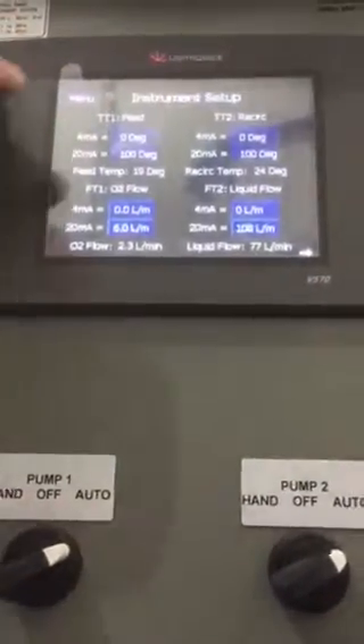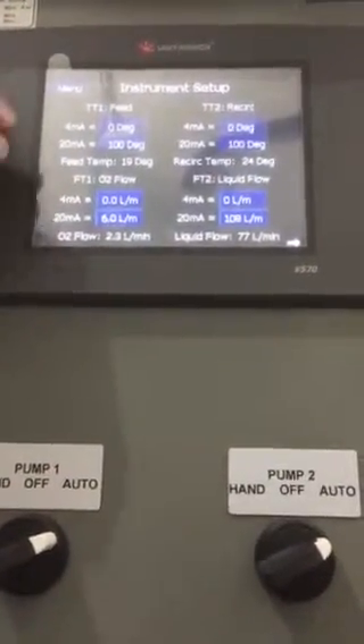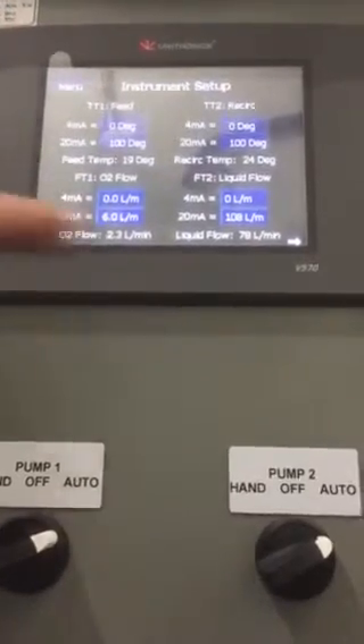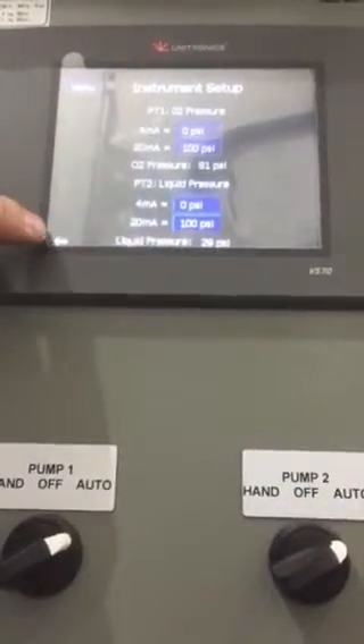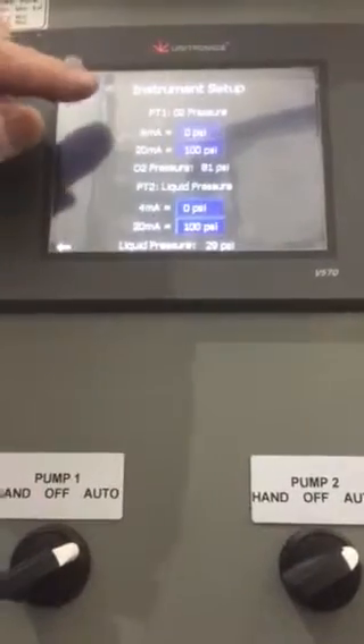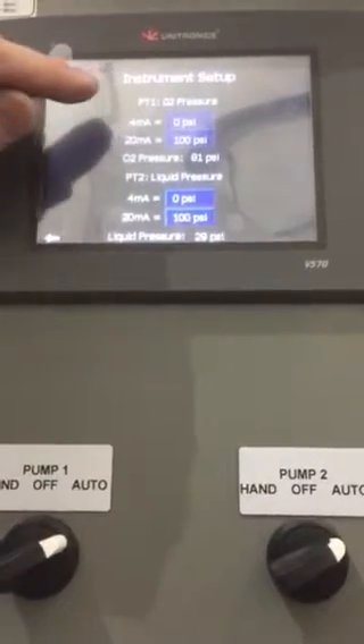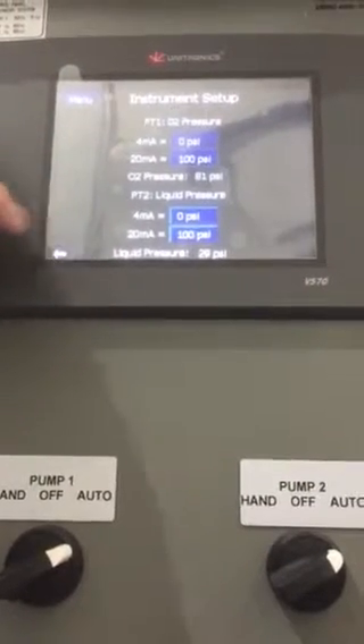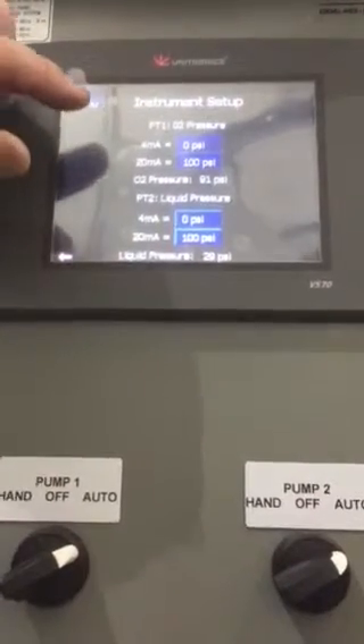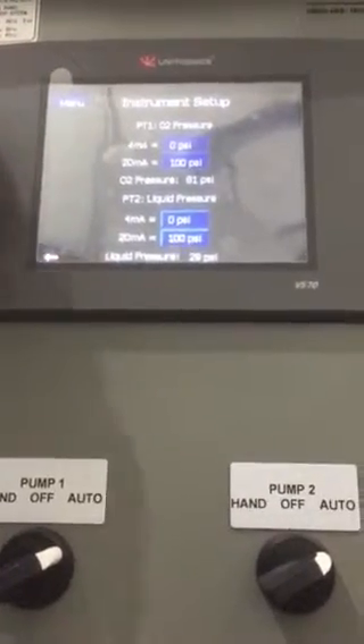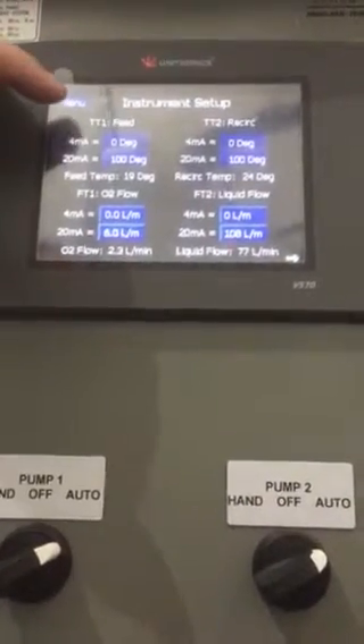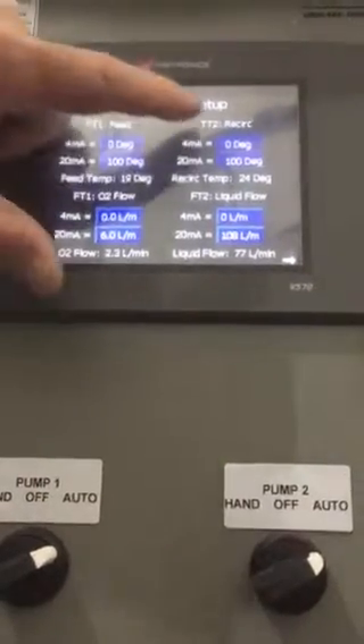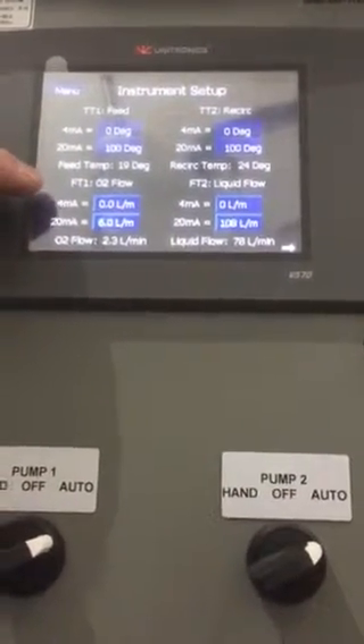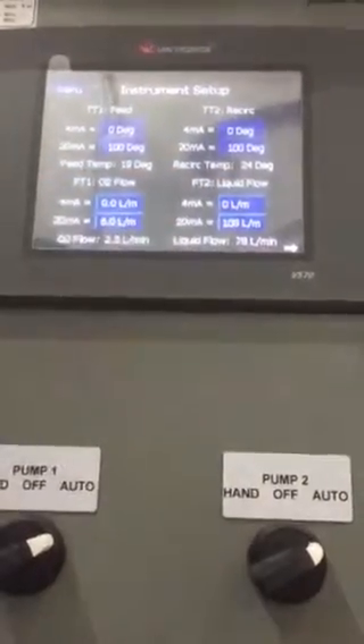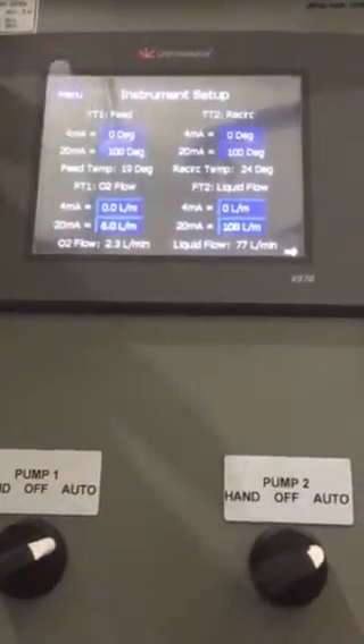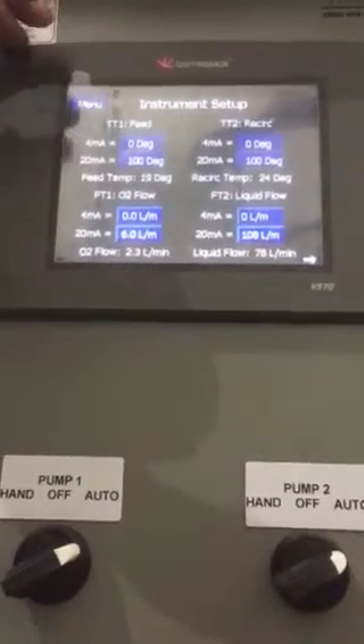The instrument setup has already been done. These are the numbers. I'll record these numbers. These are for calibration purposes. There's two screens here. If you just hit the forward and back button, all that does is it sets all the variables for the 4 to 20 milliamp outputs of all the instruments. For the liquid pressure, two pressure switches for oxygen and liquid, for the temperature 1 and temperature 2, and your flow 1 for your oxygen, and your flow 2 for your liquid flow. So those are all set right now. You shouldn't have to change them unless you get a really bad discrepancy in your flow rates.